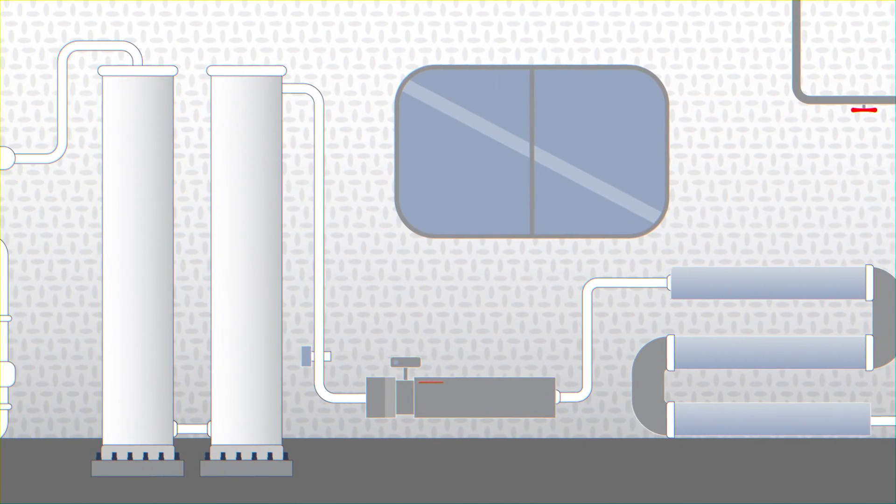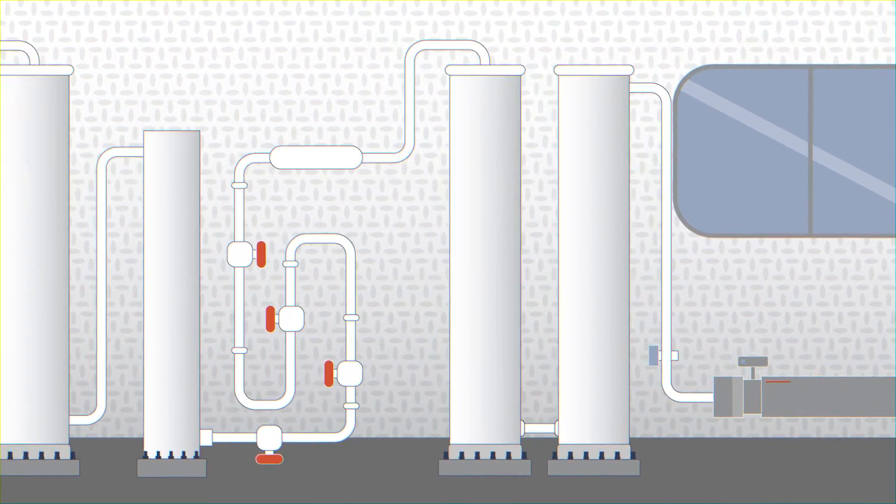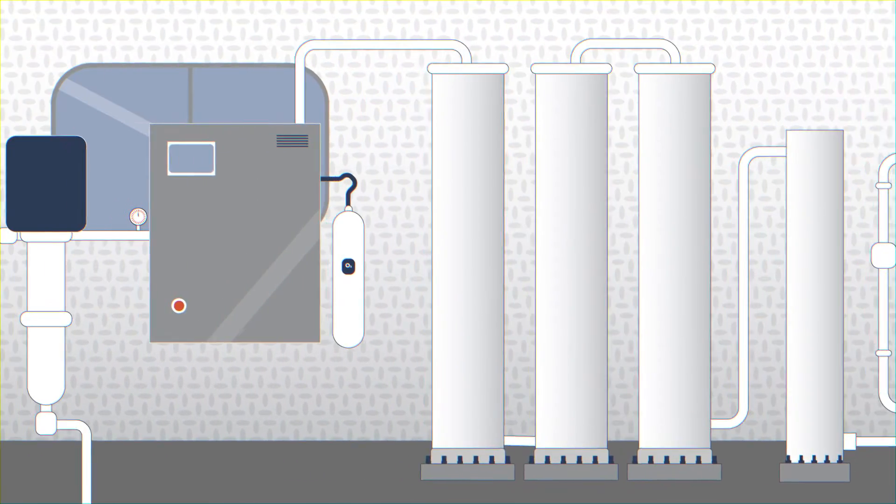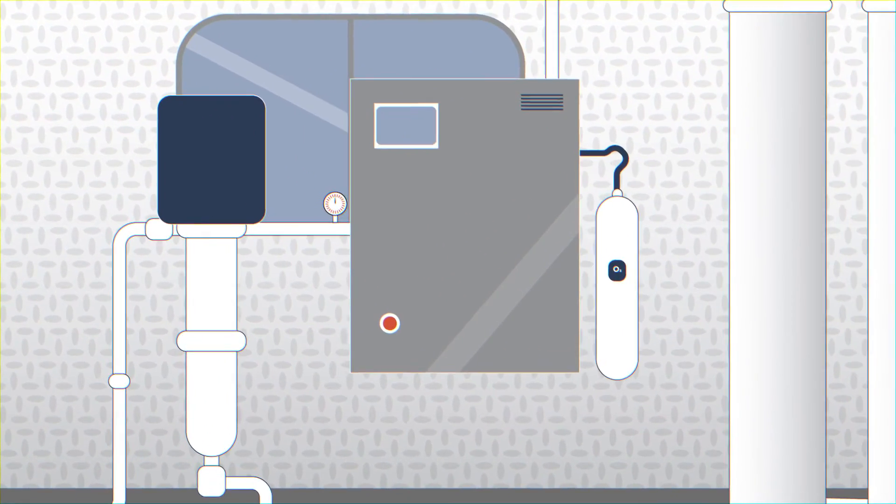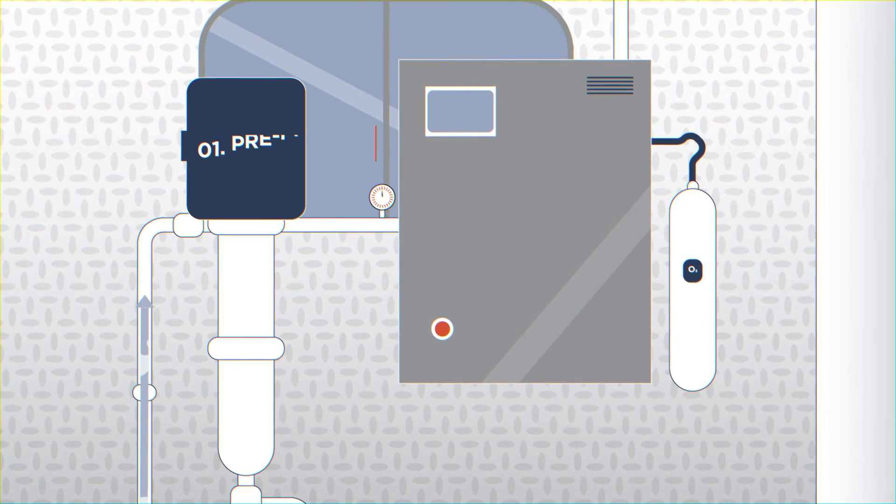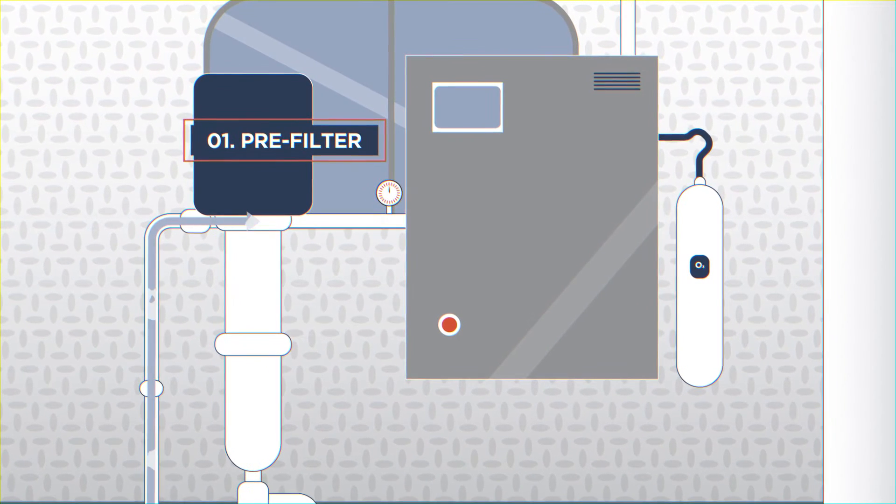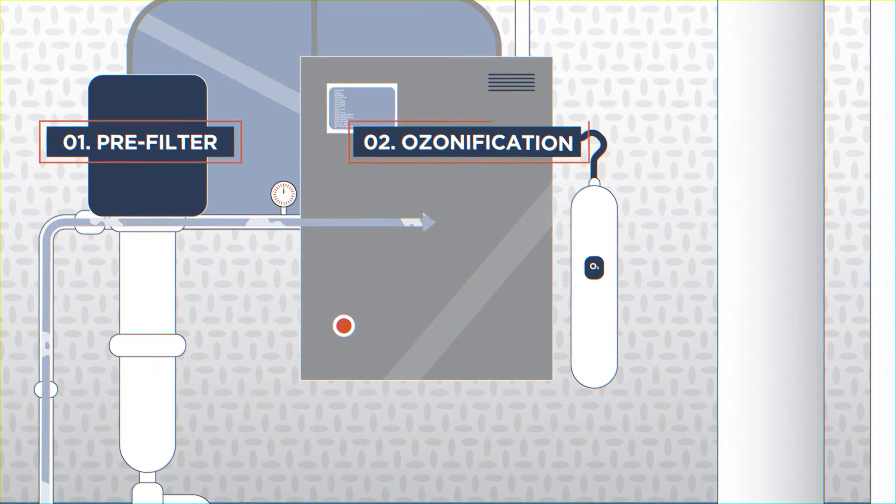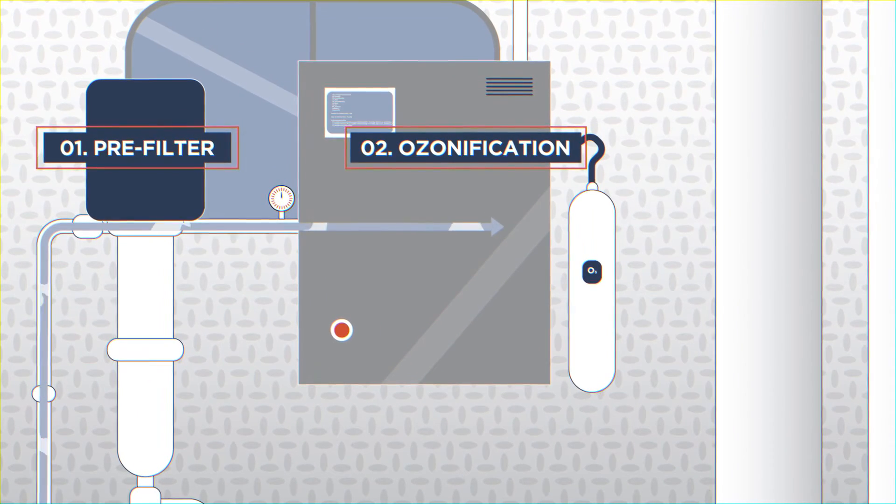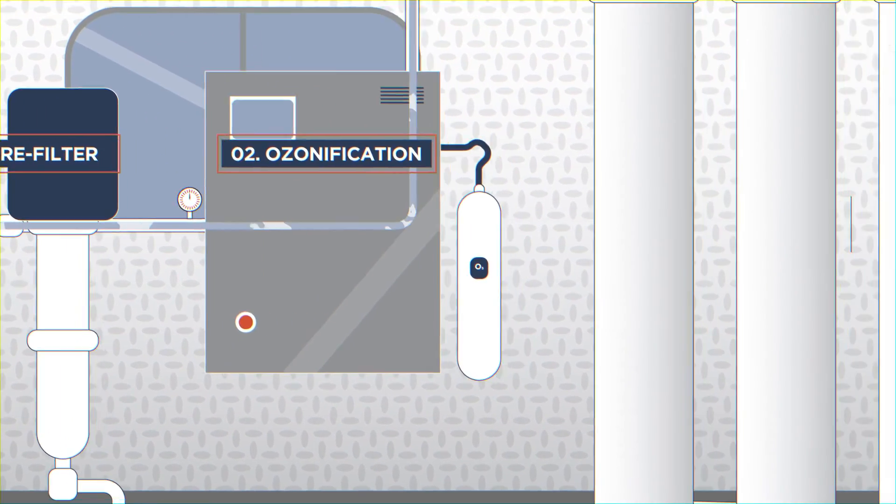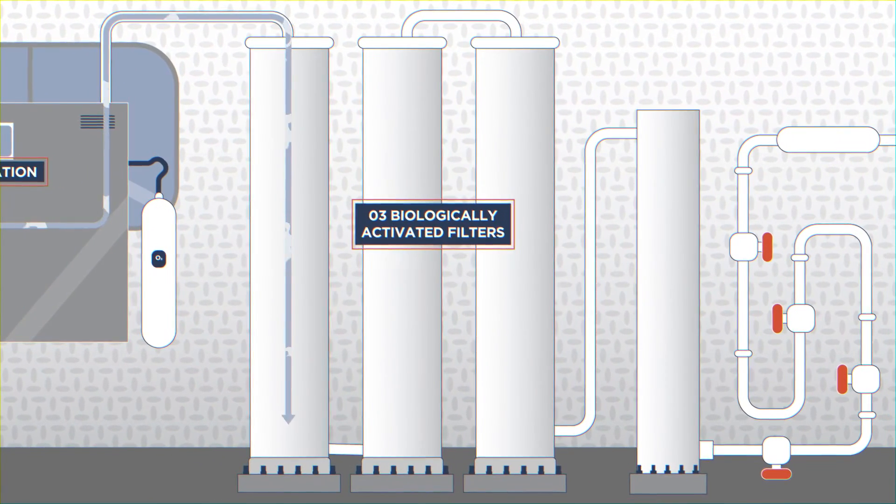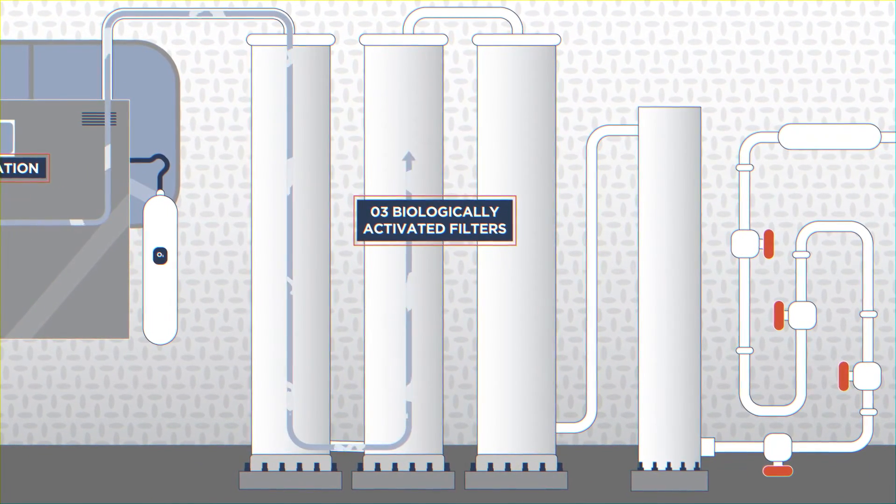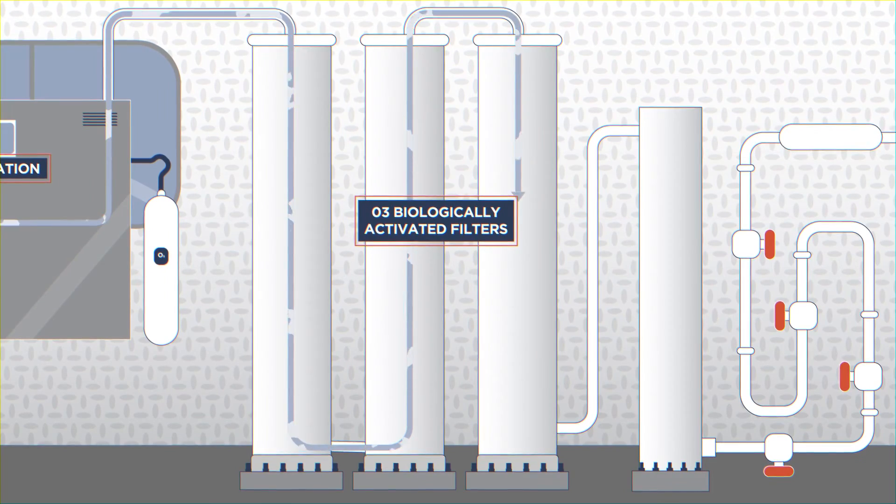Researchers at Colorado School of Mines have created a mobile DPR system with a six-step advanced filtration process. First, the water goes through a pre-filter getting rid of larger objects. Then it goes through an ozone generator to oxidize contaminants. From there, the water moves into biologically activated filters, which further break down compounds still in the water.